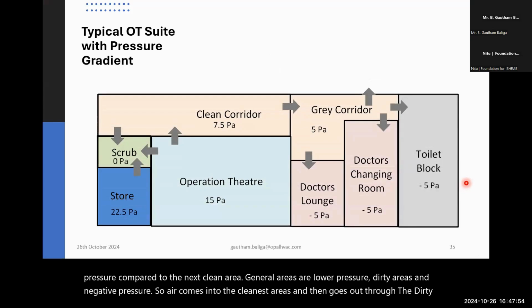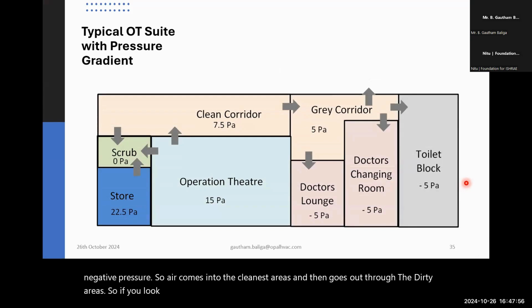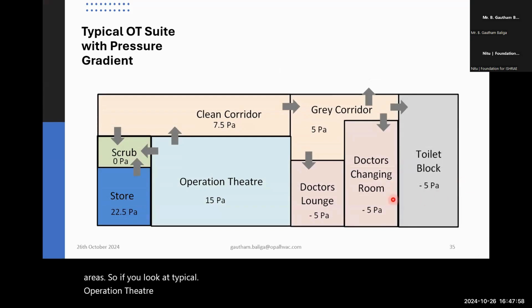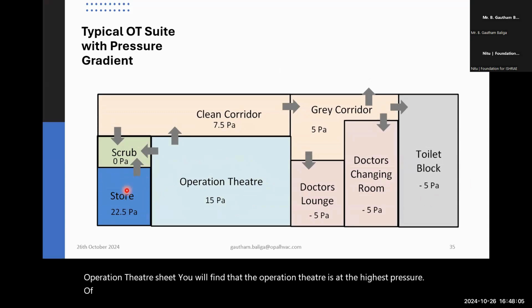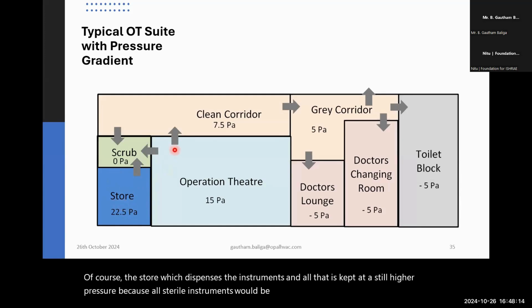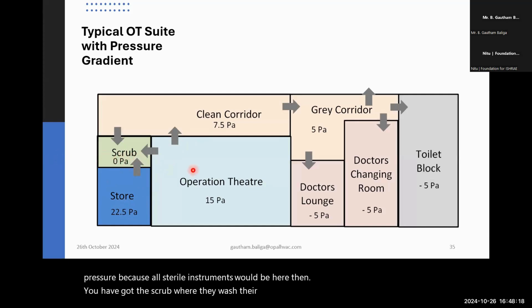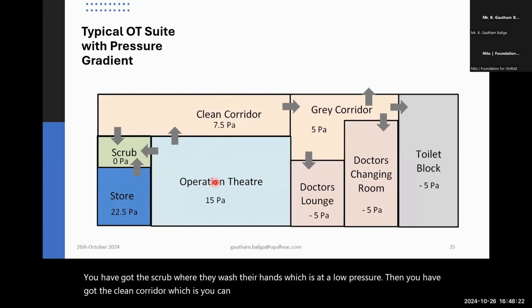So if you look at a typical operation theater suite, you'll find that the operation theater is at the highest pressure. Of course, the store which dispenses the instruments and all that is kept at a still higher pressure, because all sterile instruments would be here. Then you've got the scrub where they wash their hands, which is at a low pressure. Then you've got the clean corridor, which is, you can see, at a lower pressure compared to the operation theater.